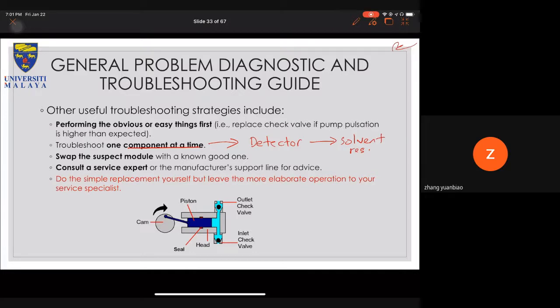But by just doing that, you are not solving the primary issue, which is how the bubble actually formed in the first place. Because you don't know where the bubble comes from, and if you cannot see it, then you will need to search by looking at each module one by one slowly. By doing this, you might want to check the tubing and the connections between each module, because sometimes they are loose, so you can introduce air bubbles from there. Bubbles might be very small, but over time you can see them getting bigger and bigger. So that's what I normally do: troubleshoot one component at a time.